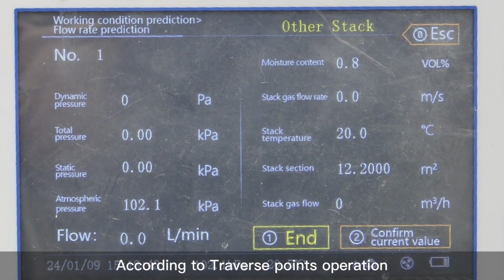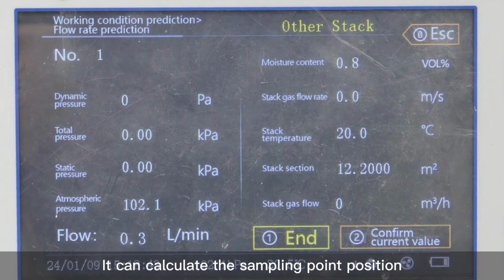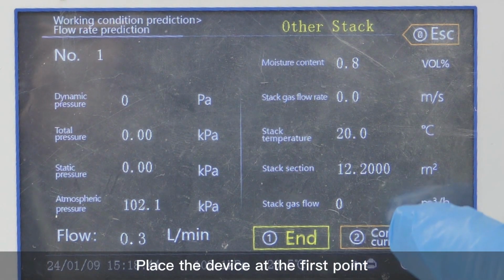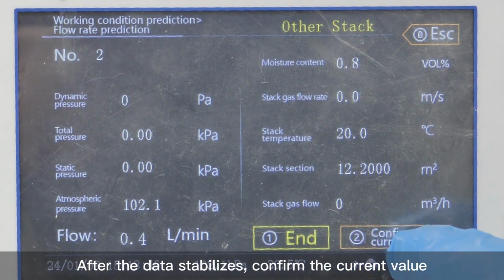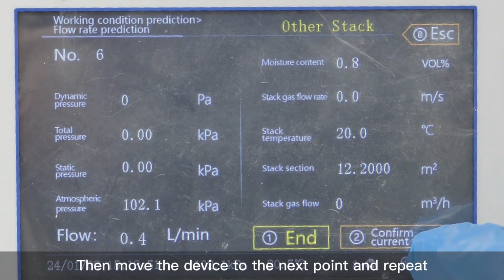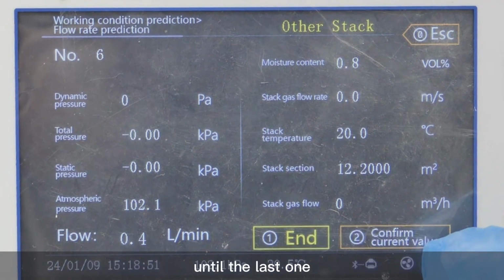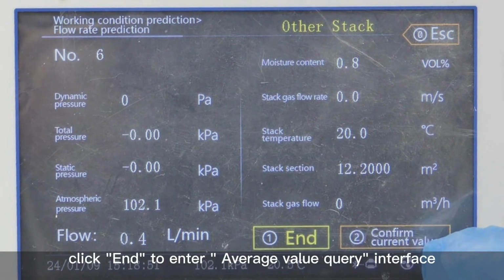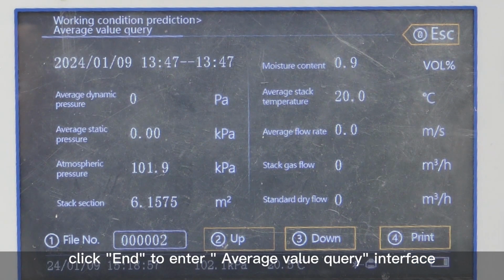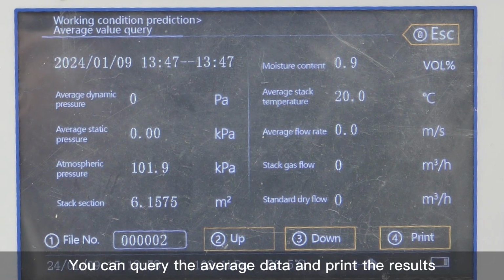According to traverse points operation, it can calculate the sampling point position. Place the device at the first point. After the data stabilizes, confirm the current value. Then move the device to the next point and repeat until the last one. When all points are finished, click End to enter average value query interface. You can query the average data and print the result.